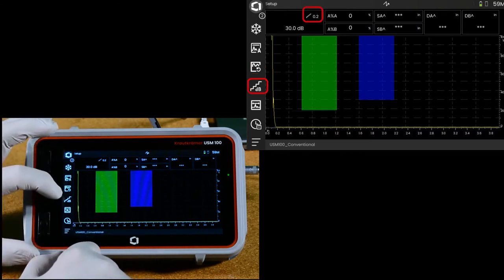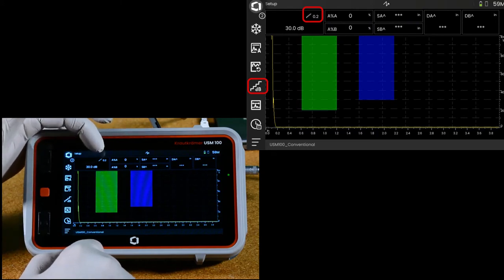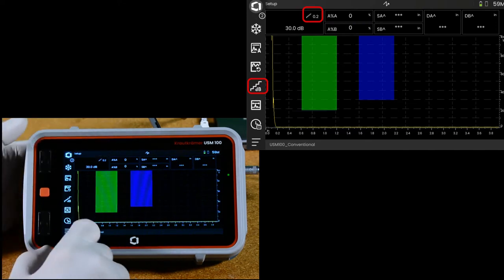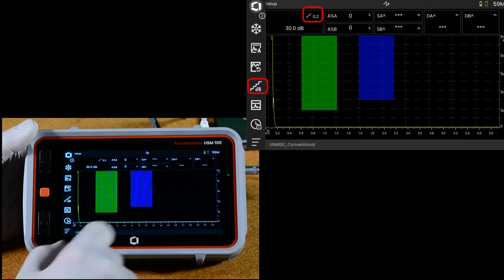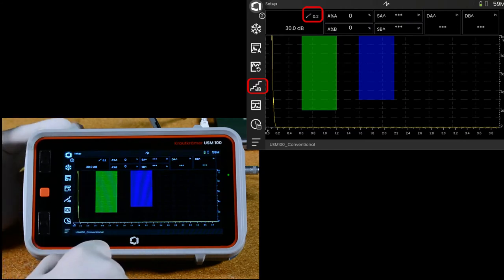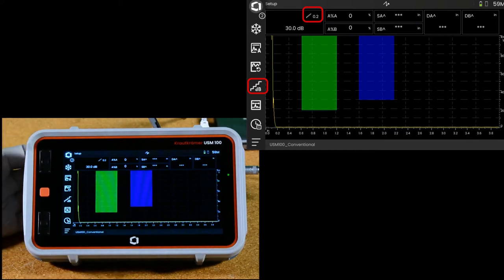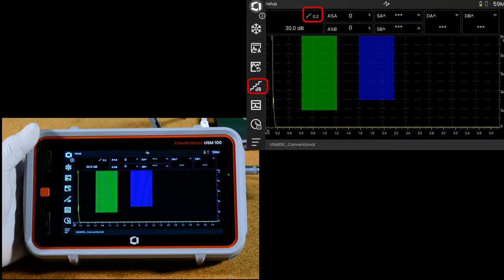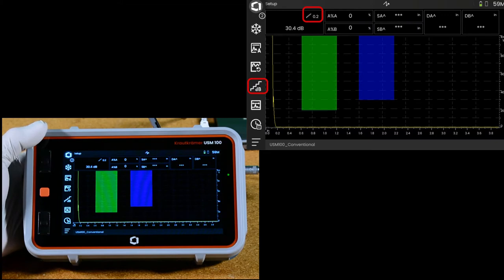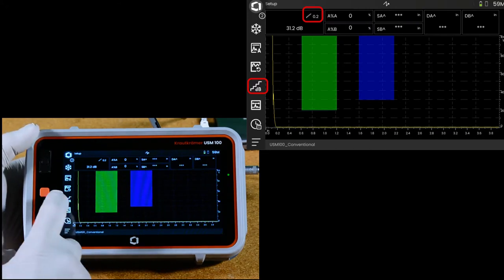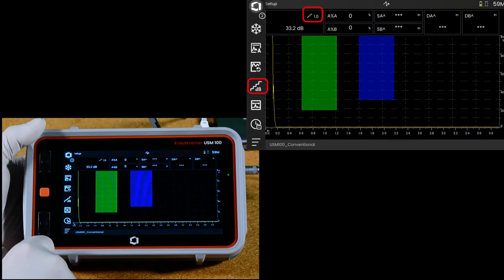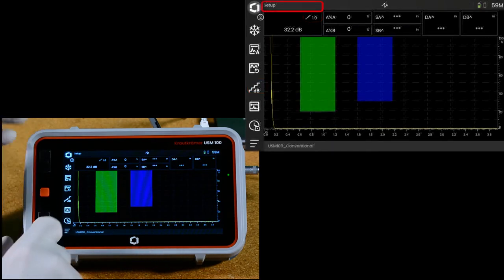One right below that is DB step. You'll notice up here in the gain control, there's a little step icon and right beside it a number. That is how much your gain will change each time you increment or decrement gain. Whether you're using the scroll wheel or the gain switch, there's a little rocker switch on the back right under your index finger when you're holding the instrument. You can increment or decrement the gain by clicking one end or the other, or you can hold it down to move continuously. By changing DB step, I hit it a couple of times, now DB step is showing as one dB. So each time I hit up or down, it's going to change by one dB. So that's the command bar.